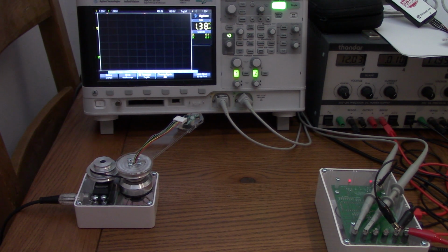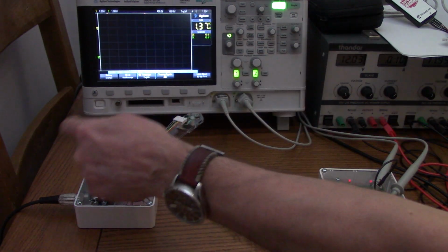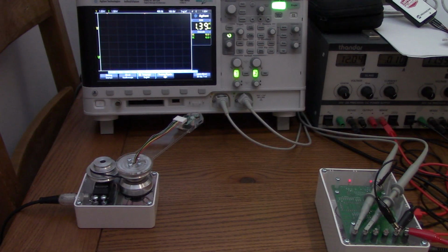What you'll see in the presentation that goes with all of this, when you've been clicking these videos, is that I've produced all the tables for the different pulley ratios, and right at the bottom of each one, you'll see the Ziegler-Nichols settings for proportional integral control. Now I've got the system set up for a 1-to-1 ratio here, and we're going to set them up in accordance with that. So we've got a K value of 2 and a time constant of 0.296.